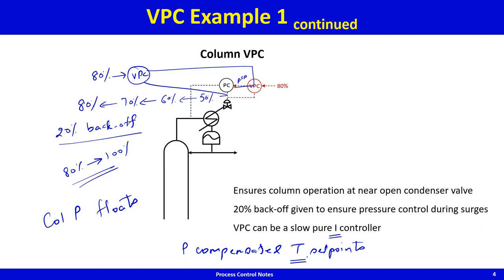How to do that? Use linear interpolation: given a composition, find the bubble temperature at a given pressure, then at a higher pressure, and interpolate for intermediate pressures. The temperature set point will come from this interpolated bubble point. The key point is that to realize the energy benefit with a temperature control system, pressure compensation of the temperature set points is required.